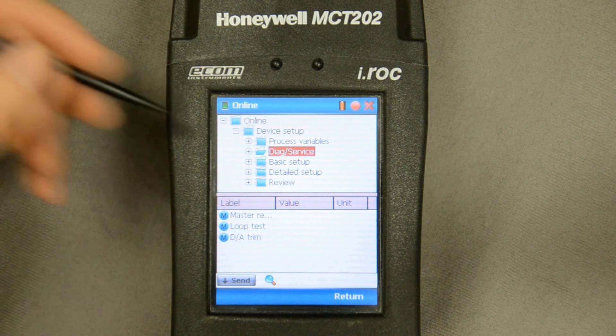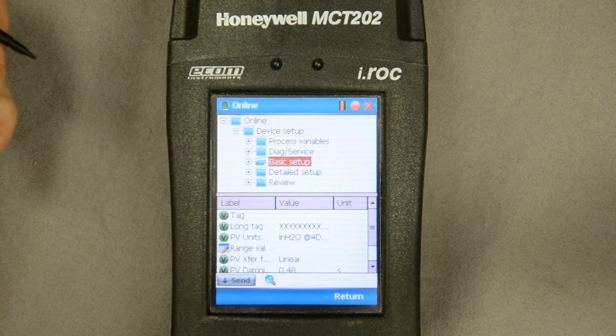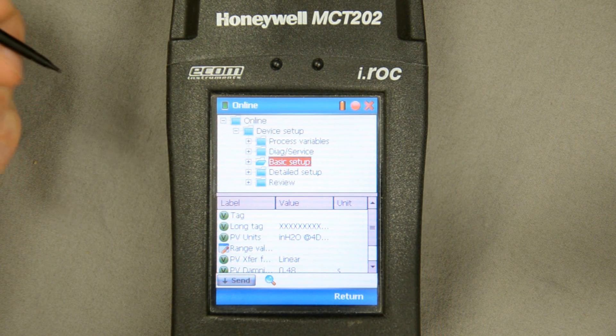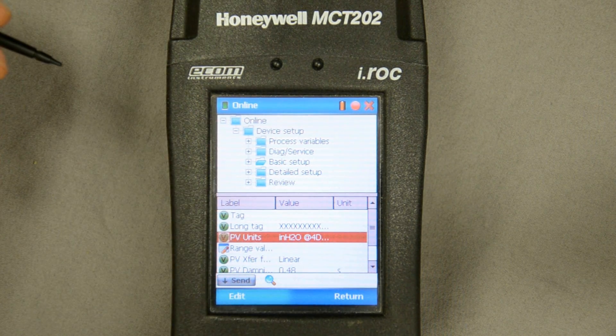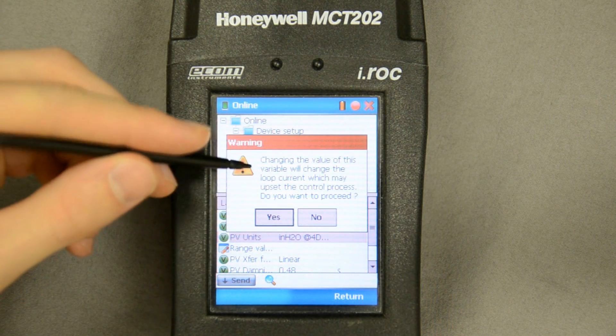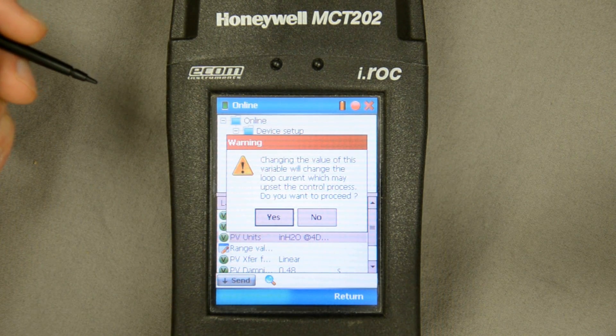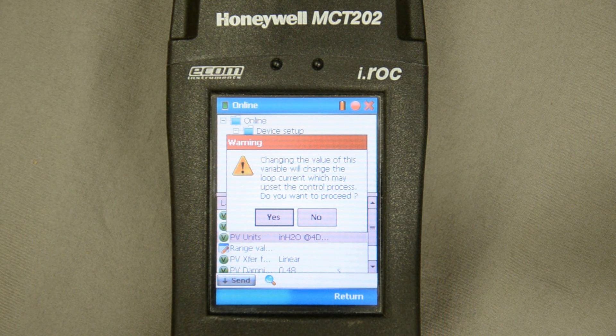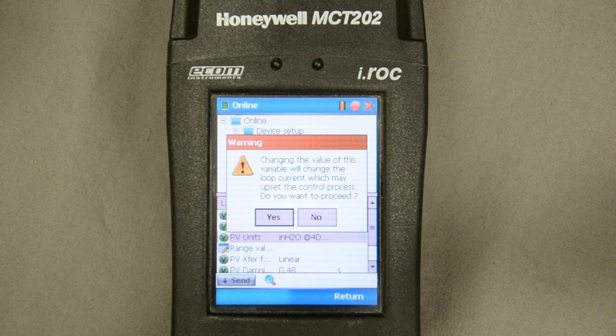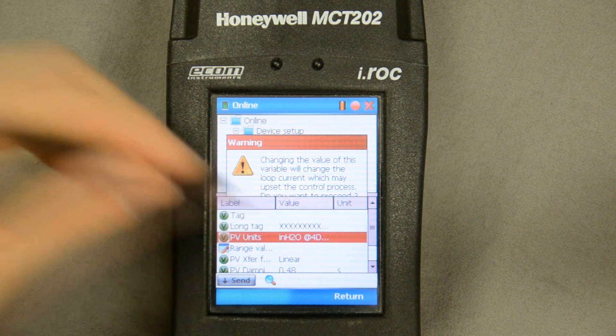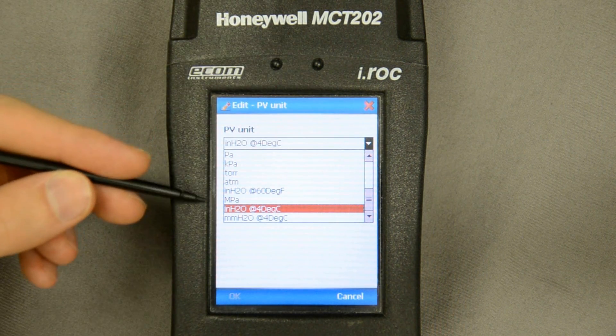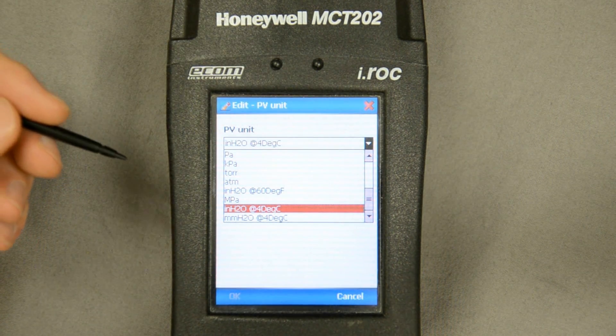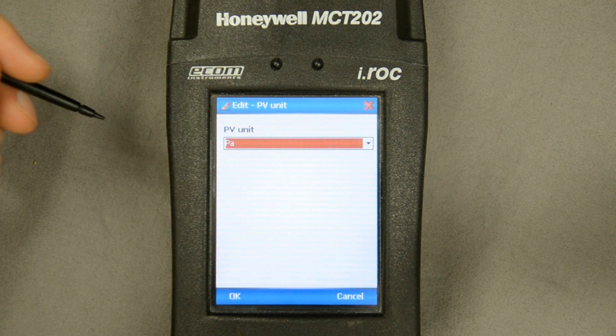On this screen it's just for informational purposes. Over here are some of the executables I can run in diagnostics. In the basic setup this is where I start doing some of the specifics of changing configuration, which you would normally do on a transmitter. Right now I can change the transmitter setup. There's a warning screen reminding me that if I make any changes while it's connected to the process loop it could cause a process upset. I'll proceed and change the engineering units — from inches of water to inches of mercury, millimeters of mercury, Pascals, whatever I want.